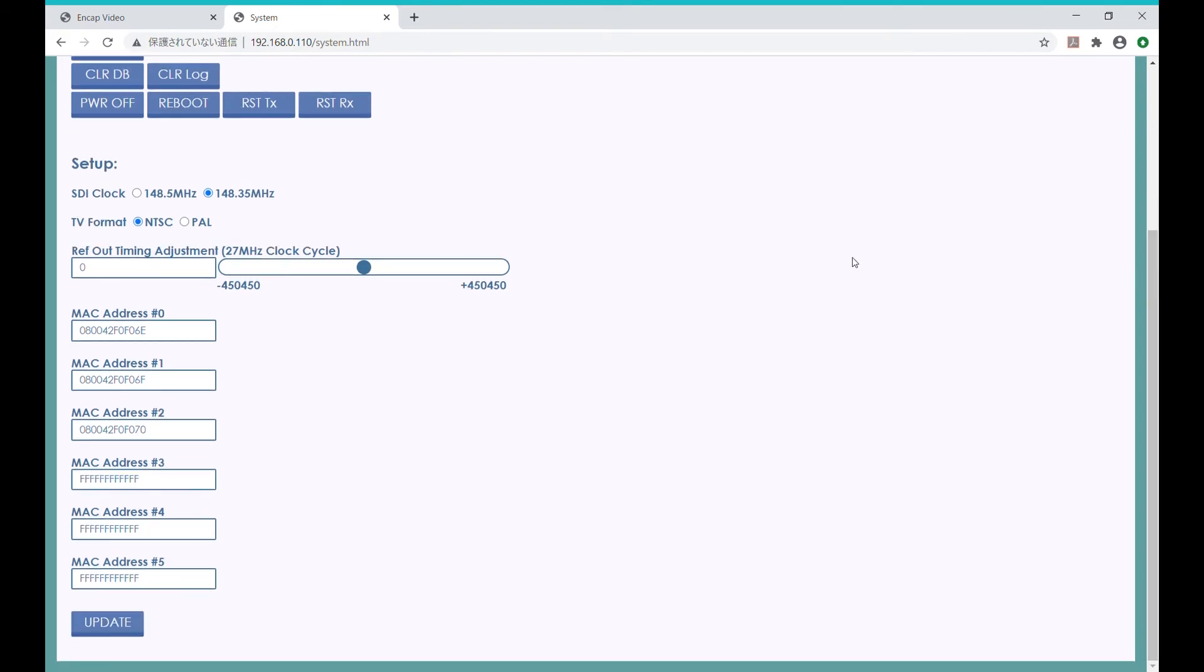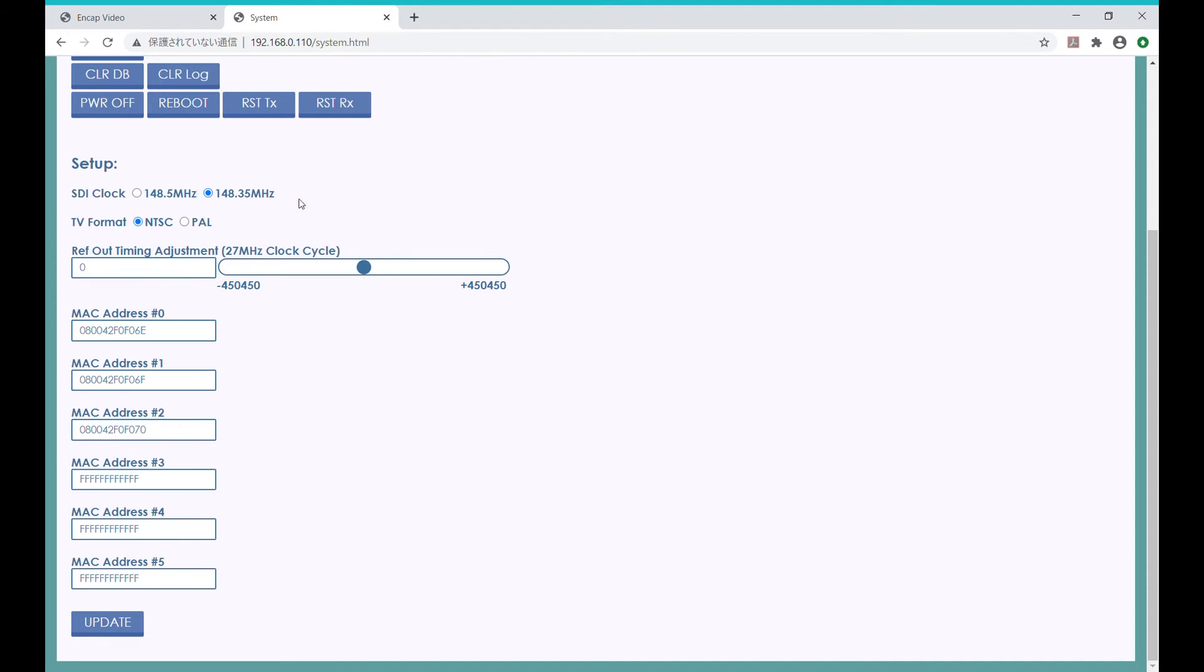Down here, we can set the clock used for the SDI ports, which depends upon the frequency that we are using. For instance, we are now using 59.94 Hz, which means that we need to choose 148.35 MHz. If your video is either 50 or 60 Hz, then you will change this setting to 148.5 MHz.